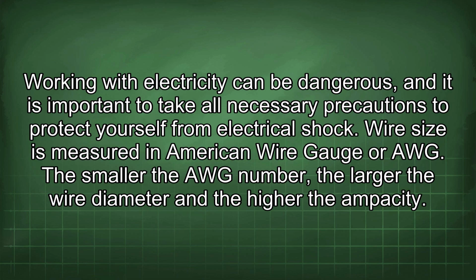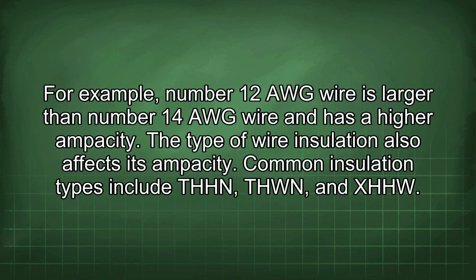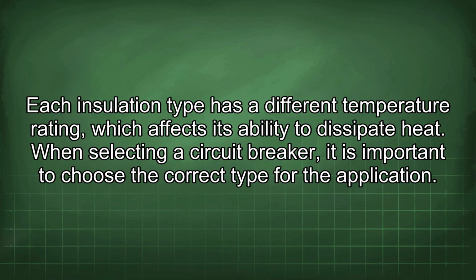The smaller the AWG number, the larger the wire diameter and the higher the ampacity. For example, number 12 AWG wire is larger than number 14 AWG wire and has a higher ampacity. The type of wire insulation also affects its ampacity. Common insulation types include THHN, THWN, and XHHW. Each insulation type has a different temperature rating, which affects its ability to dissipate heat.